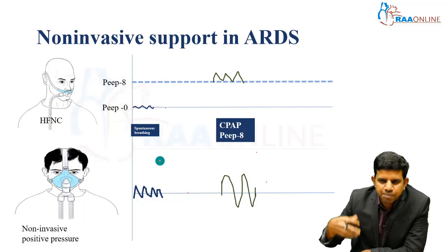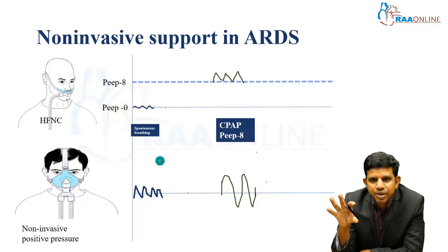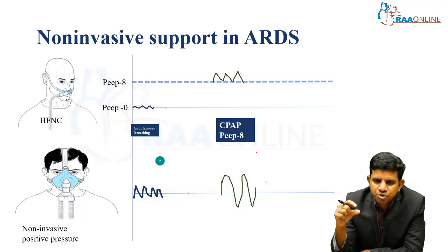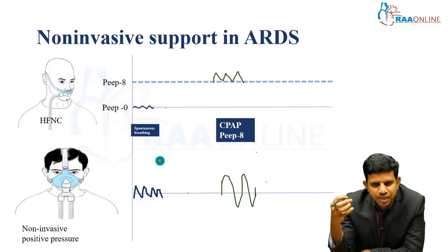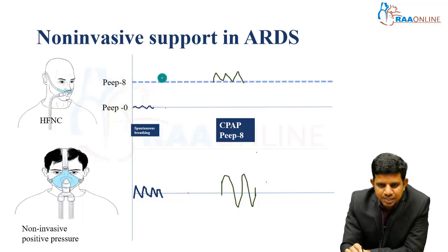The second thing is CPAP. CPAP means you only deliver a positive end expiratory pressure. If you want to deliver CPAP on an ICU ventilator, you just set a PEEP and FiO2. The patient will determine how much tidal volume they want to take. You just set a PEEP. For example, I set up CPAP with a PEEP of 8. My patient will take breaths at the level of PEEP. In the face mask, there is no PEEP. The patient will take breaths, inspiration and expiration, at 0 PEEP, so the pressure will be 0. If I apply an external PEEP through CPAP of 8, the patient will initiate and breathe in and out at a PEEP of 8.